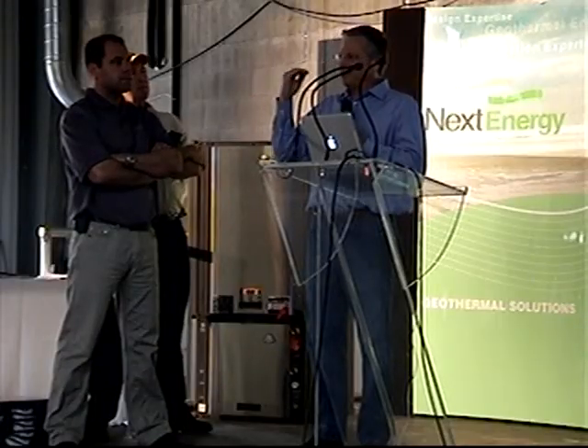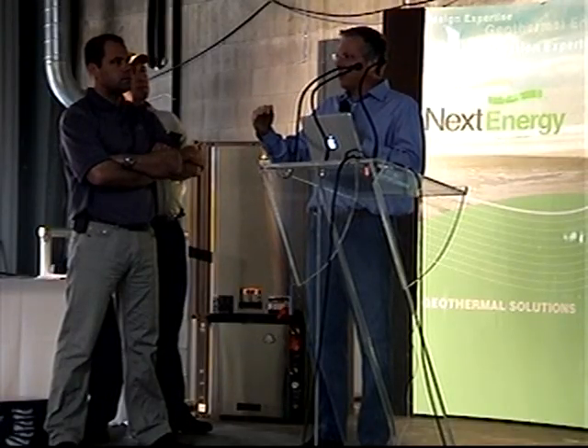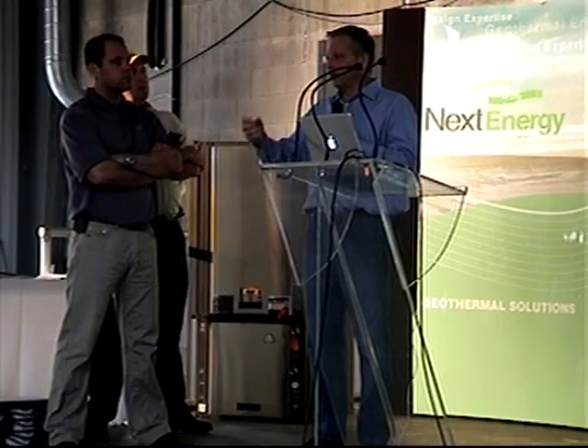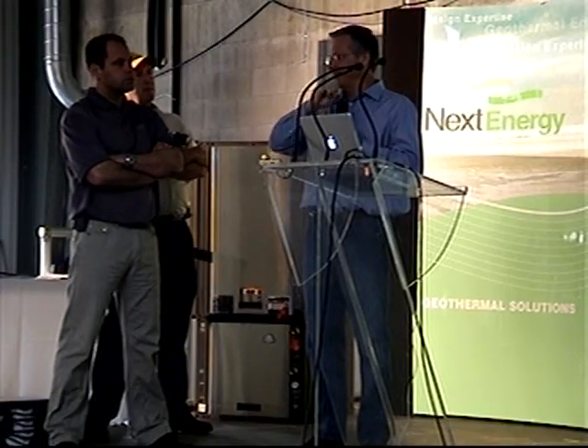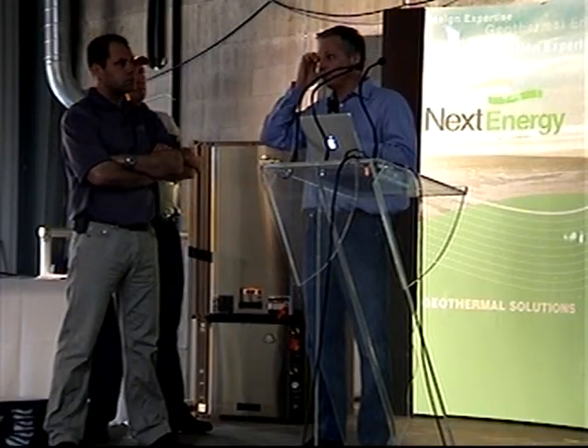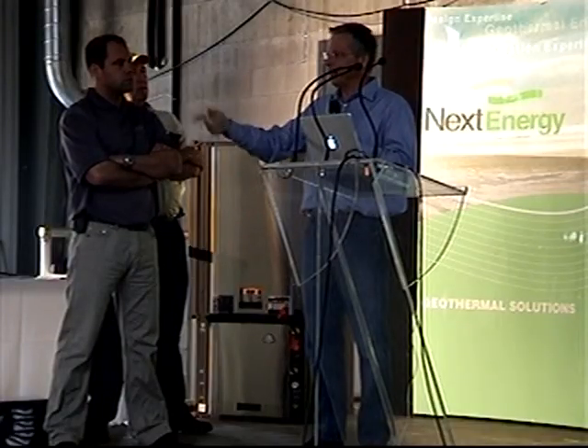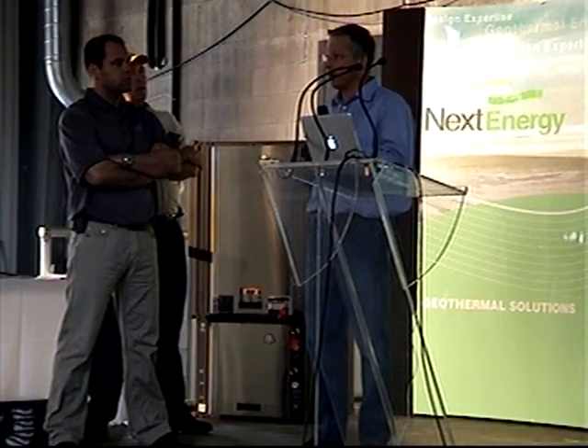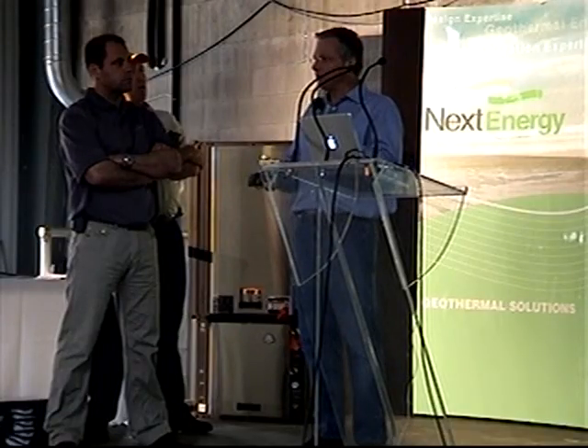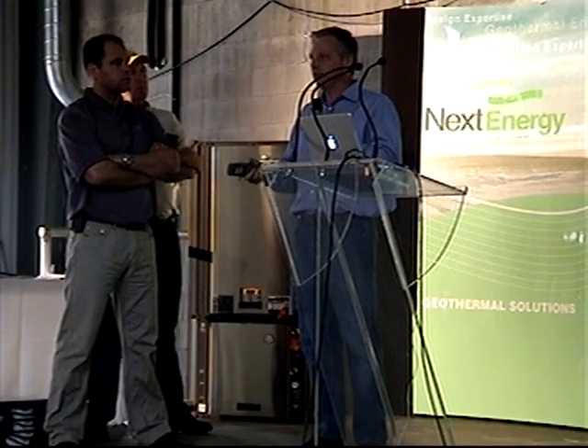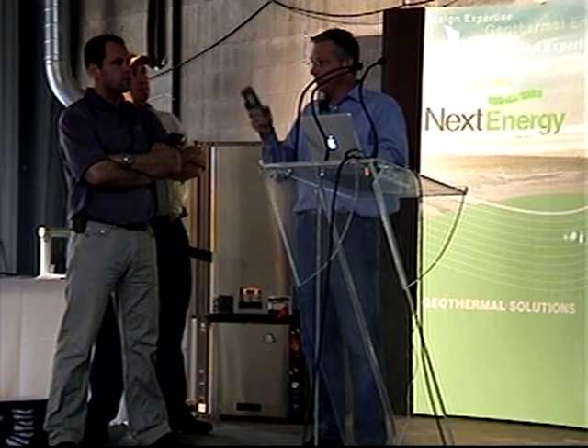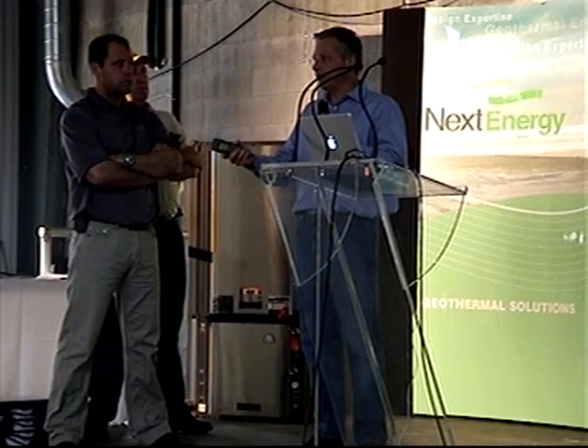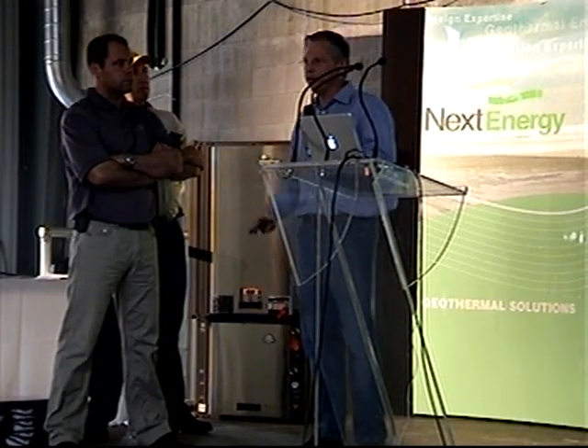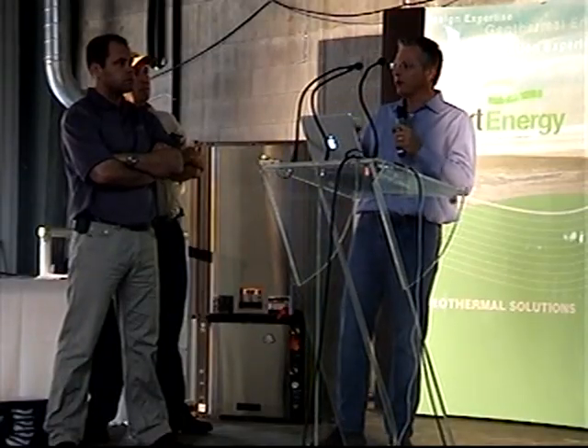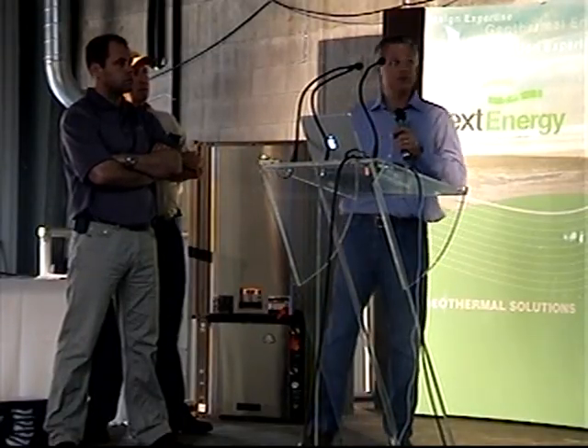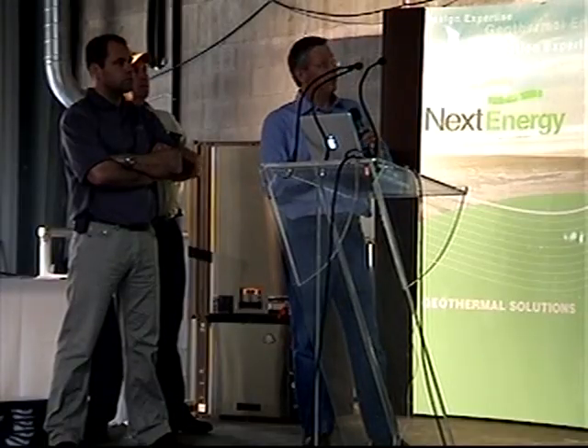If the unit's running steady for 3 hours, we want to make sure that we didn't lose charge. Let's say you had a catastrophic leak. A fitting blew, you lost all your charge. You wouldn't want the unit running then for days and days and days and never shutting off, and then the compressor burns out. So every 3 hours we stop just for a couple minutes. It probably takes 4 minutes because of the time delay. Stops, says, hey, do I still have charge? Yep, goes again. Now you'd only ever see that if your unit's been running steady without shutting off for 3 hours. But that's how we do this.